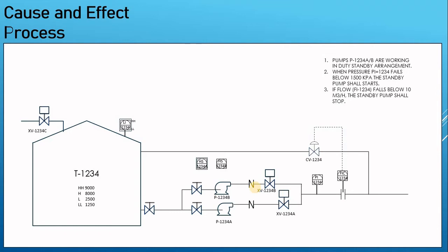Now the second pump is running — both of them are running. Assume some users had stopped using the flow, so flow will be reduced and pressure will be gained and increased again. At this point we depend on the flow: if the flow is less than a certain value for a certain time, we need to stop the standby pump again. If the flow rate is reduced even further, you open the recycle valve so you have a minimum flow through your pumps.